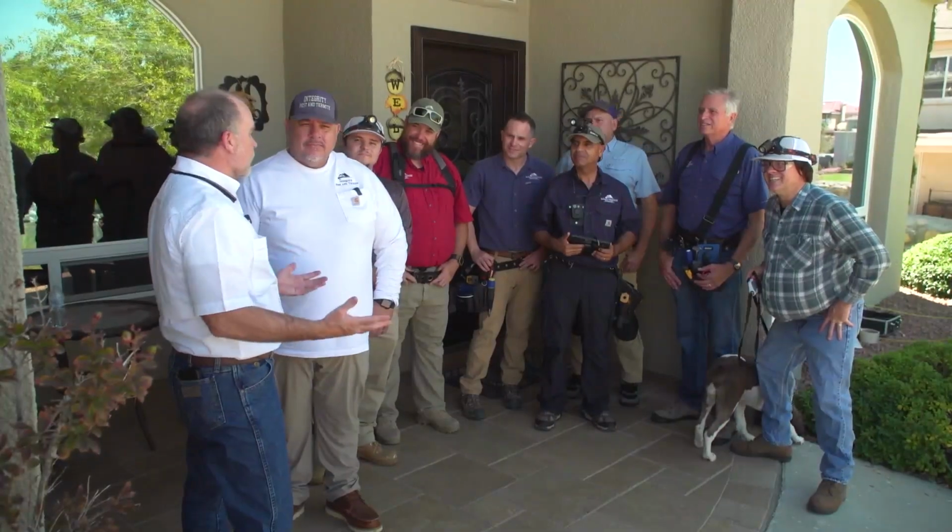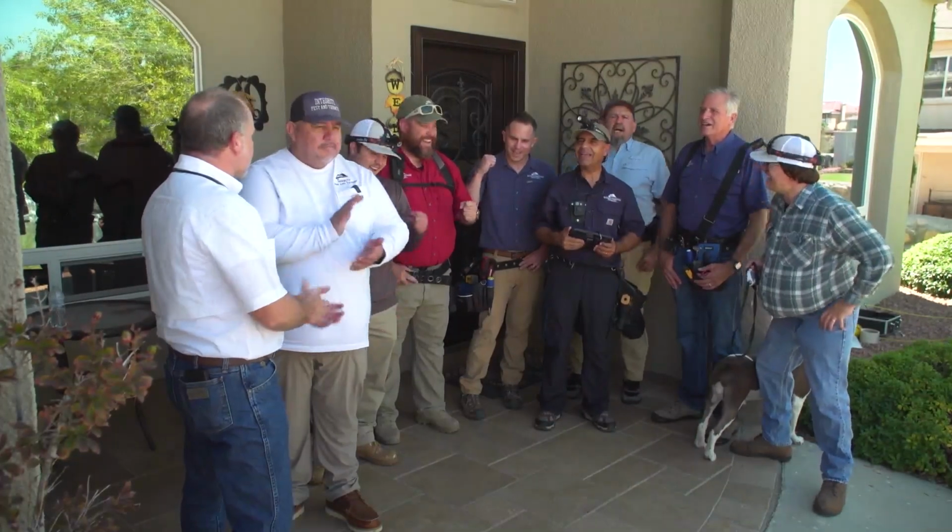Okay, everybody, I think we had a wonderful inspection. Let's hear what we found. All right. Did a thorough termite inspection all around the house. Home is termite free. On the electrical panel box, we had an issue. Once we pulled the cover off, there was a double tap at one of the breakers. The breaker's supplying power to two separate circuits.